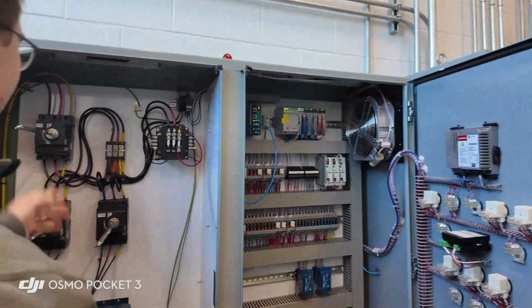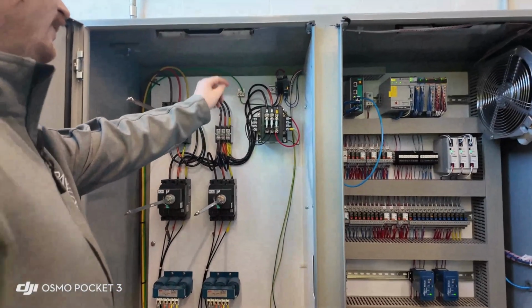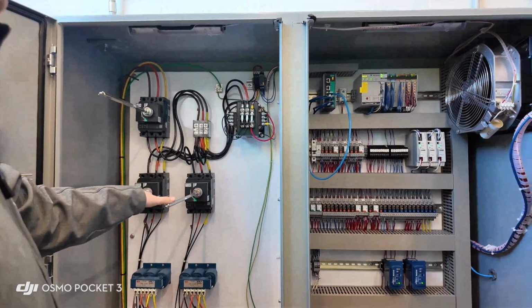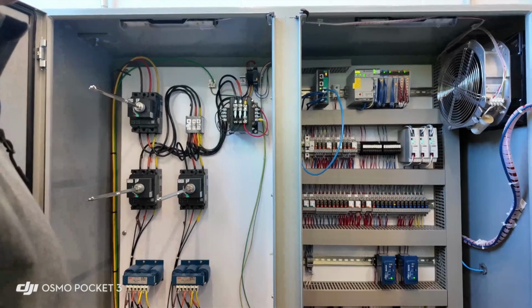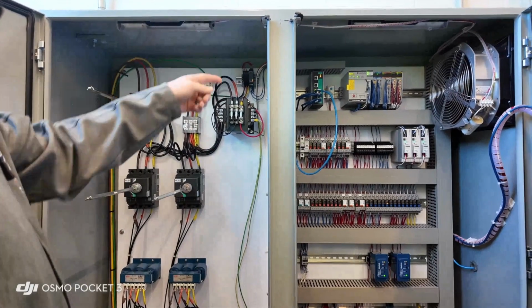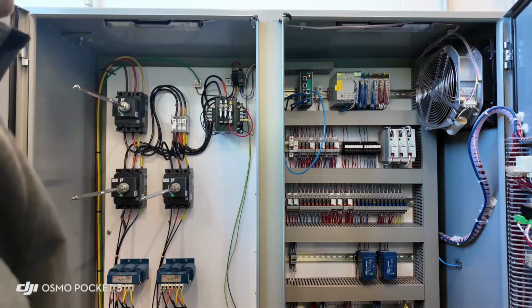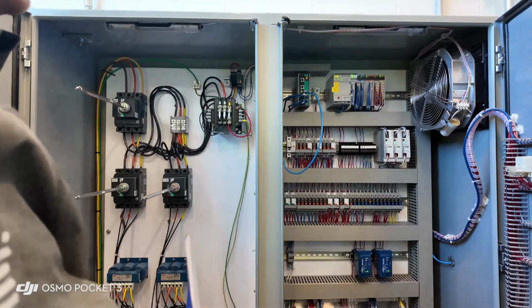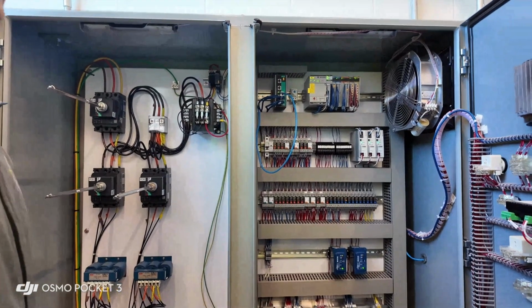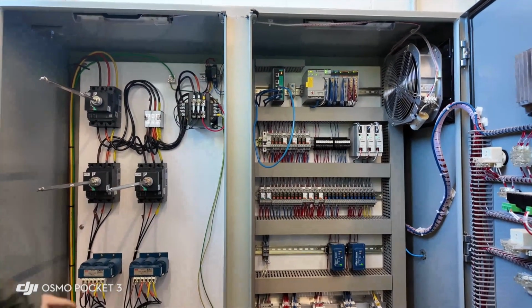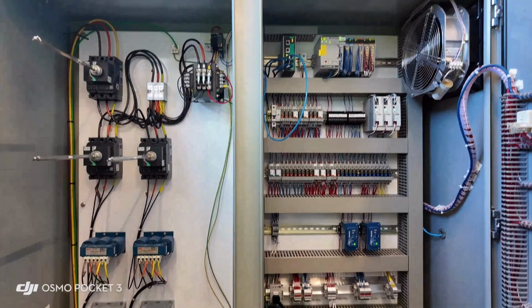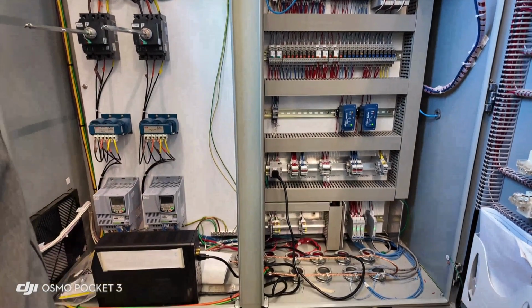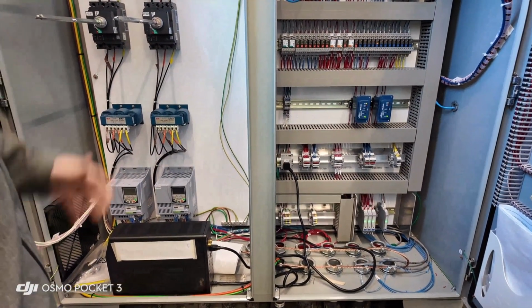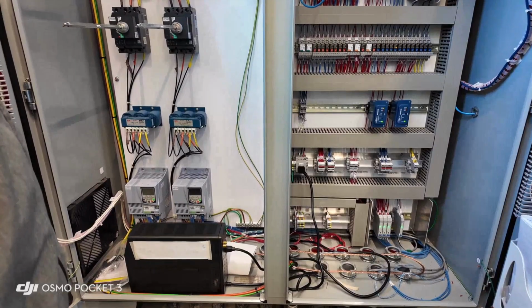So inside, like I said, main breaker, it's going to feed to your distribution block that's going to get fed to both your pump breakers and the control transformer. We also have a phase monitor in here to monitor the voltage on each phase. If one of the phases cuts out, it's going to send you an alarm saying the other phase failed. So down here we have line reactors, and it's just going to improve harmonics that's going into the drives, prevent any surges or inadequate voltages for the drives.